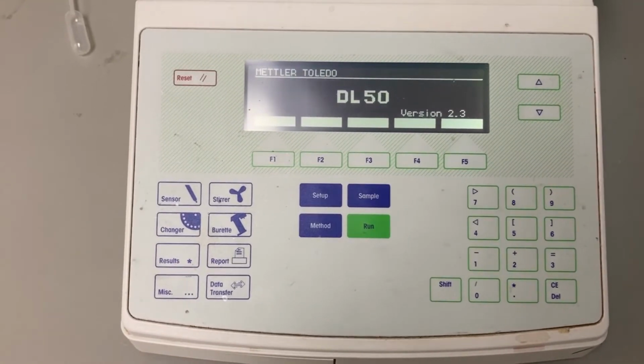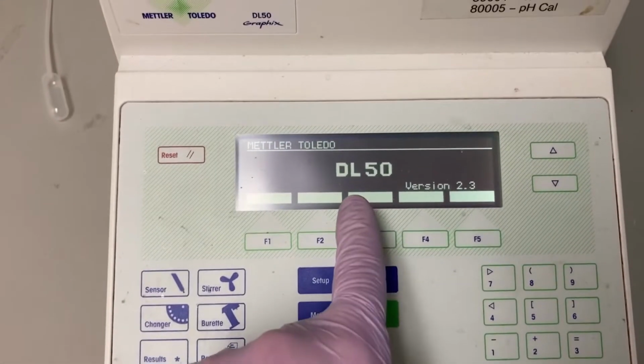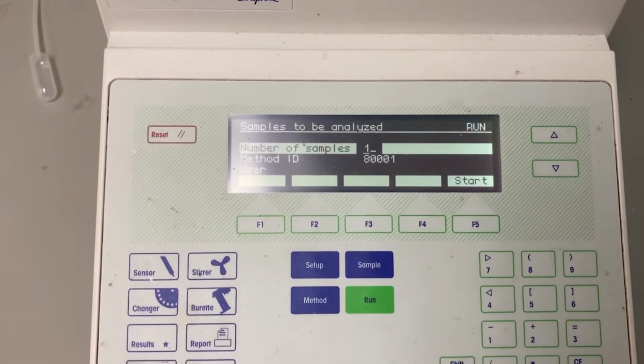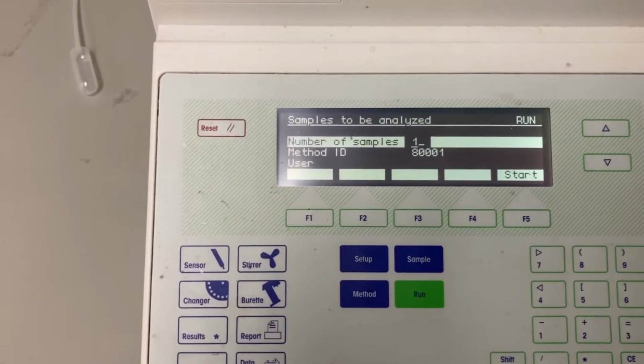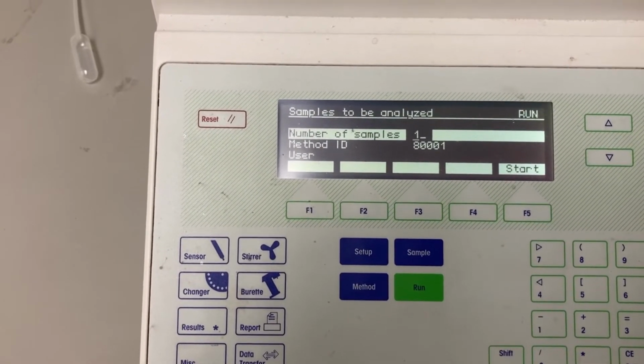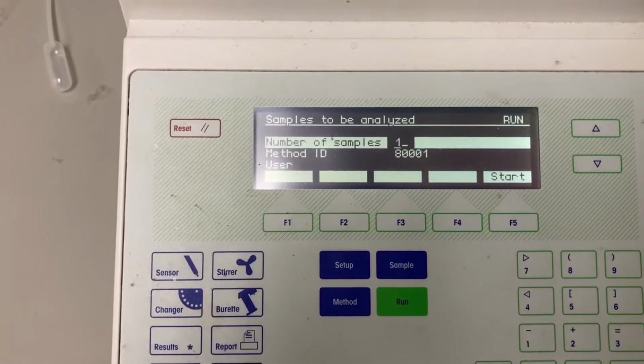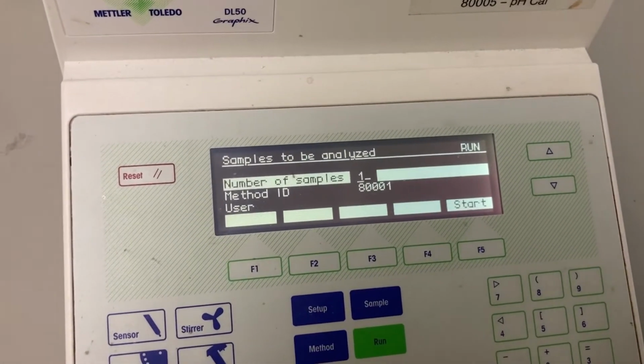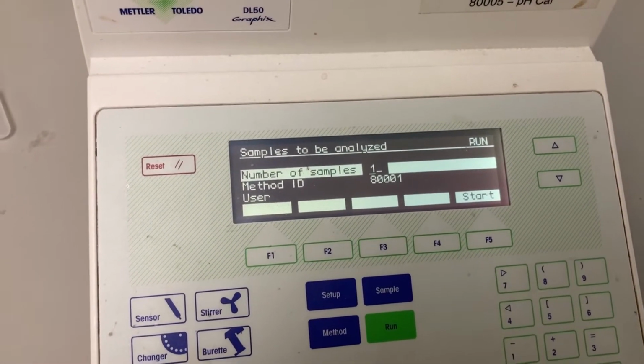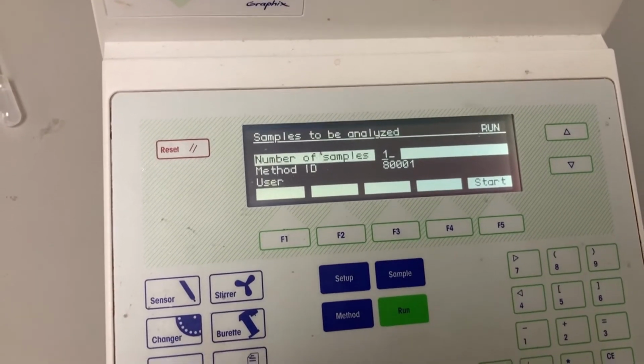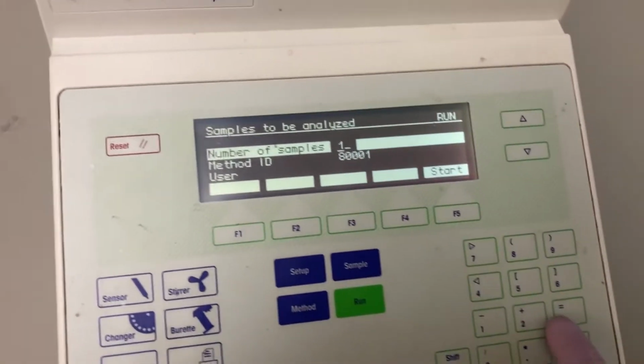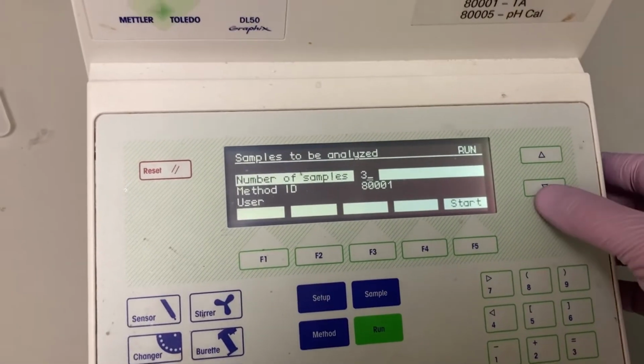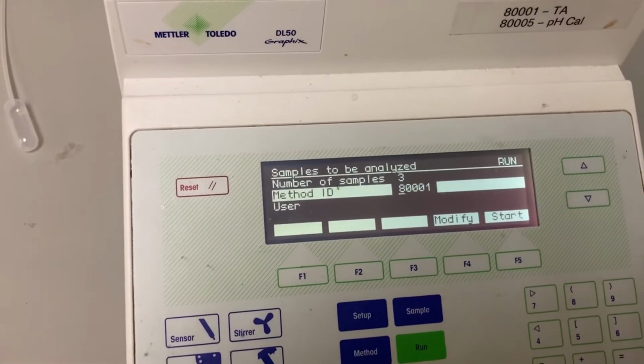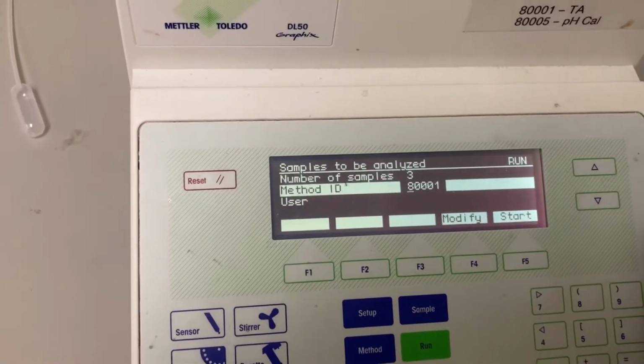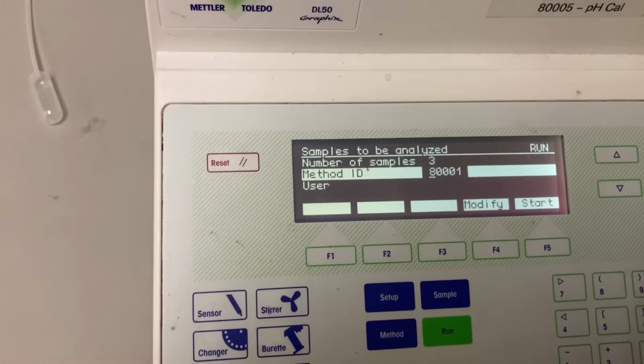Once the AutoTitrator has booted up, you'll see this screen. Then you want to hit run, and it will take you to this screen, and we're going to want to set up a calibration. We will be calibrating with the 4, 7, and 10 pH buffer. So you're going to want to change the number of samples to 3, and then go down, and this AutoTitrator has saved methods. So there's a specific method we need to enter for calibration. Both are written down here.